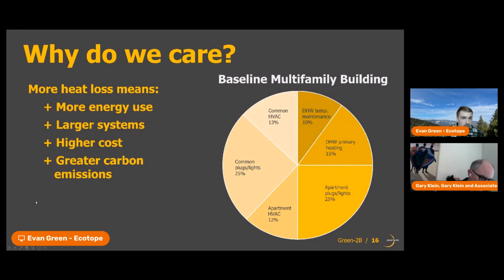To do that, let's look at the energy usage in a typical baseline multifamily building. From this pie chart, you can see that about a quarter of the energy provided to a typical multifamily building is accounted for by domestic hot water heating. And within that 25% of energy usage for domestic water heating, 10%, or almost half the water heating load, goes towards this temperature maintenance loop. So that is almost half the energy going into the system that isn't actually used by the occupants. So we want to find the best ways to minimize this temperature maintenance loss, as well as the delivery heat loss that's baked into this primary heating percentage.